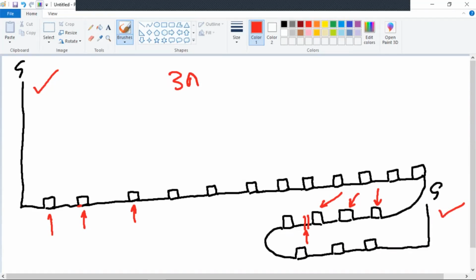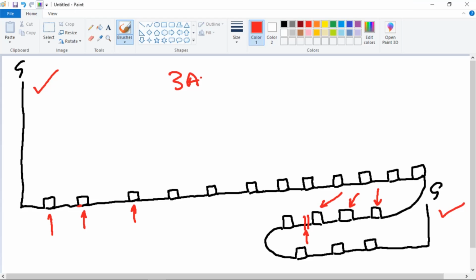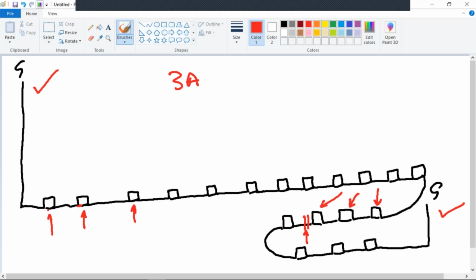3 amps. Okay. Now, when you install them in the field, and there's an easy way to do this, most of the fault indicators that come in the box, the ones you're going to install, are already faulted. They're meant to come that way for you to reset them. Whenever you get a shipment of indicators that come in a box, and usually they come 25 to a box, they also include a reset magnet. All you have to do is wave the magnet across the indicator, and it's going to put it to neutral. All right. So you're going to install all of these after you set them to neutral.